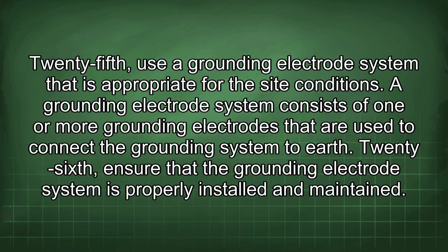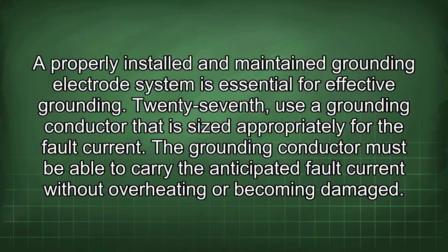25th, use a grounding electrode system that is appropriate for the site conditions. A grounding electrode system consists of one or more grounding electrodes that are used to connect the grounding system to earth. 26th, ensure that the grounding electrode system is properly installed and maintained. A properly installed and maintained grounding electrode system is essential for effective grounding. 27th, use a grounding conductor that is sized appropriately for the fault current. The grounding conductor must be able to carry the anticipated fault current without overheating or becoming damaged.